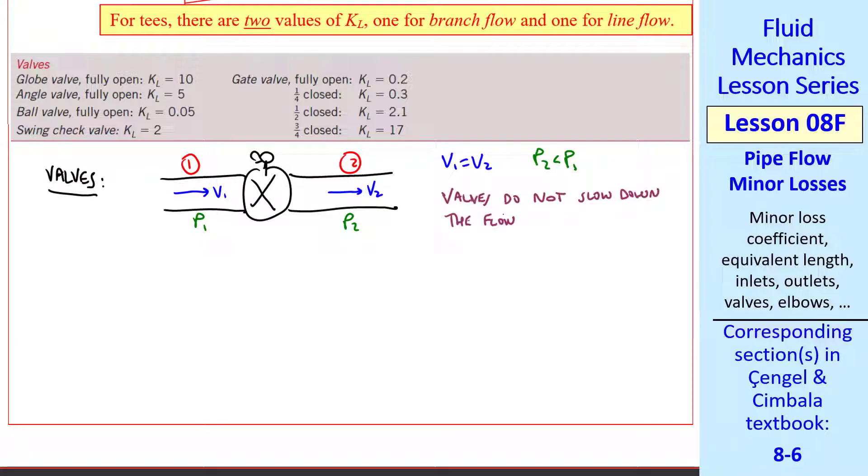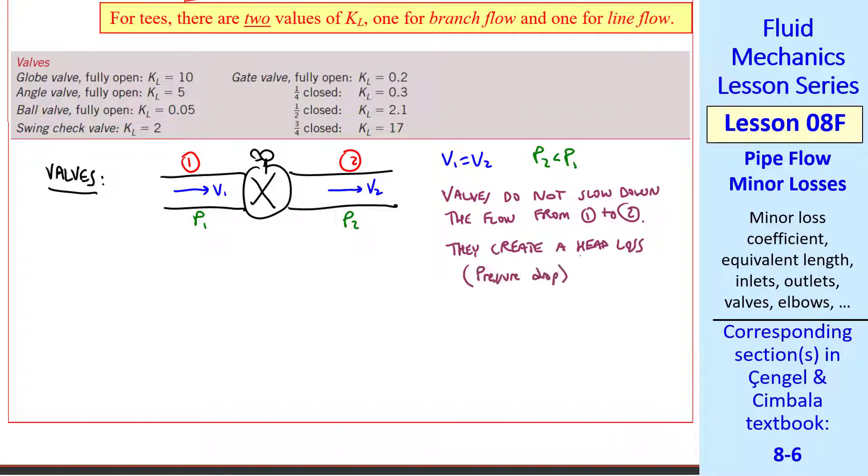Here's where students get confused. Valves do not slow down the flow from 1 to 2. Rather, they create a head loss, or a pressure drop, that slows down the whole system.